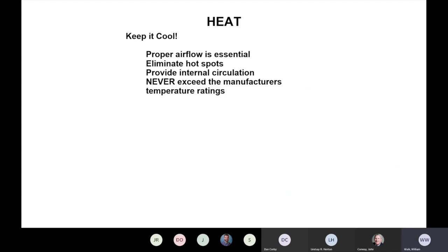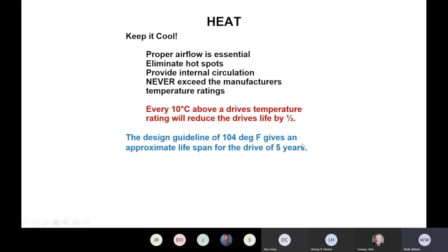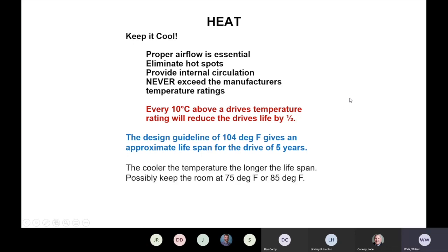We have a couple of guidelines established for this too, so that you can determine the appropriate lengths above and below for clearances for our VFDs. And you never want to exceed the temperature ratings that are published. For every 10 degrees Celsius above your drive's rated temperature rating, it will reduce the drive's life by half. What I see a lot of times is whenever a VFD specification is written, it's going to be set to run at 104 degrees Fahrenheit, which is the maximum that we can go for with the VFD. That's only going to allot for 5 years of life. So the cooler that you can keep it in the enclosure or where the VFD is, the longer it's going to last. So 104 degrees Fahrenheit is only good for 5 years.